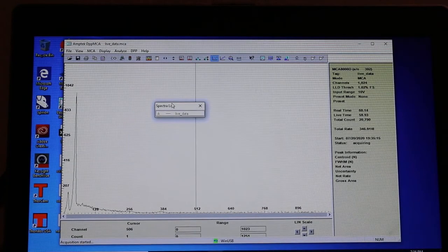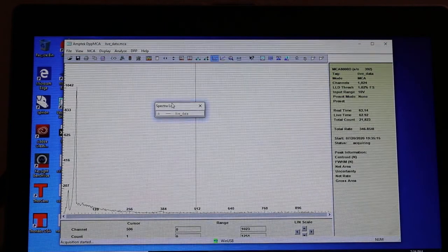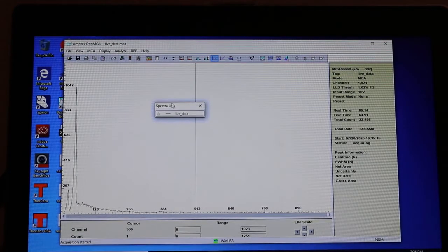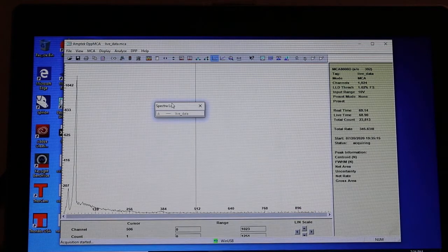The last data file will run then is a really long cesium 137 one, and that'll be the one that you'll do a bunch of calibration and analysis on. But that's it then for taking gamma ray spectrum.